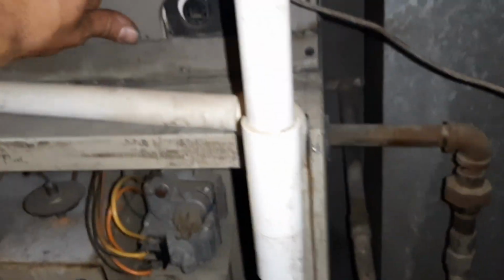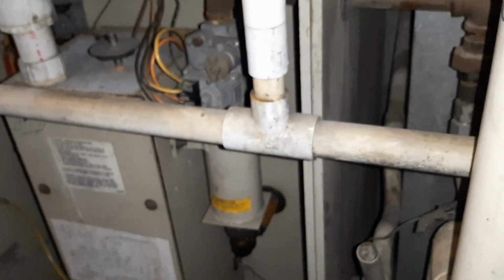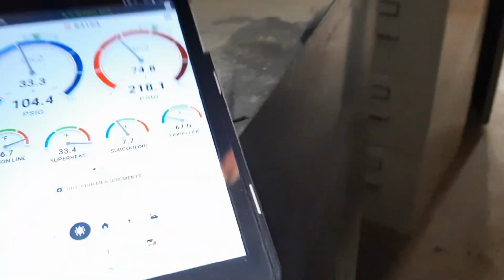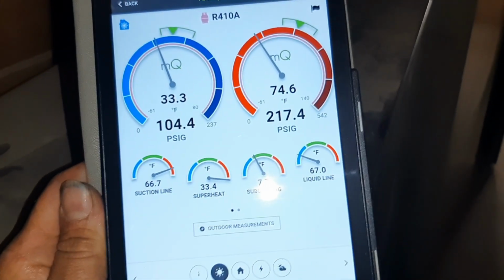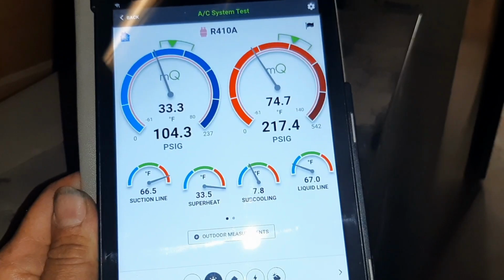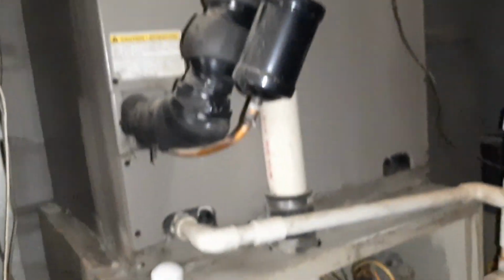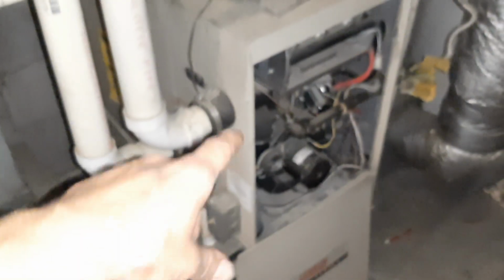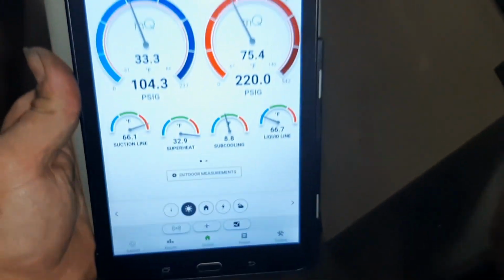These furnaces are from 1984. So, I mean, we cleaned the secondary the best I could, but this thing is not going to be perfect, that's for sure. As long as my superheat comes down, we know we got airflow issues. Obviously we're gonna recommend that all of this stuff be tore out and start over. You might be able to spare the AC, but these furnaces need to go. This one's been hacked up and missing all the wires, pulled off and everything else. I actually fired the heat on the other two, so they did run. But they're gonna have issues out of these things.